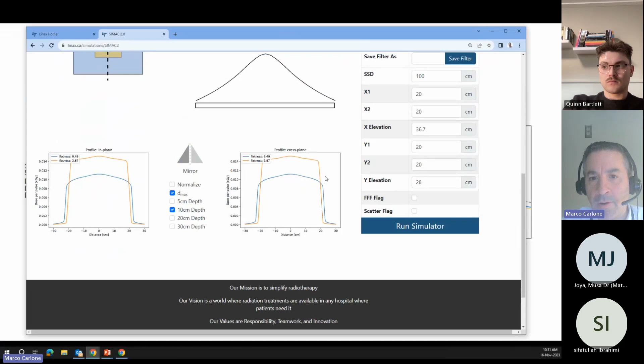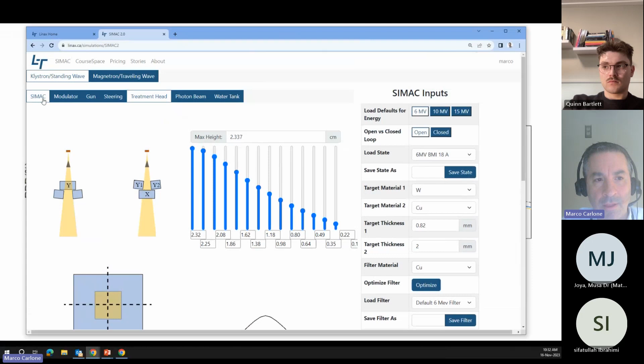The beam is still striking the flattening filter that we use for a 6 MV beam, and so the attenuation is going to be very different, right? We can see this here on our profiles, where on our D max profile over here, the beam is more intense at the center and less intense at the sides, because the flattening filter is not designed to attenuate that beam to a uniform distribution. So again, it's the same thing.